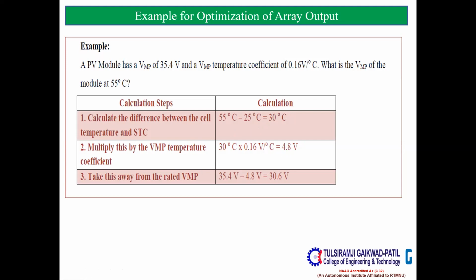This 4.8 volt is to be taken away from the VMP of this particular module, which is available in the data sheet of that solar PV module. 35.4 volt is the VMP which is given to us, and if we take away 4.8 volt, we get 30.6 volt, which would be the actual output of that PV module if the cell temperature reaches 55 degrees Celsius. You can see the VMP was 35.4, however we have got 30.6 volt from that module if its temperature increases to 55 degrees Celsius with respect to the STC of 25 degrees Celsius.